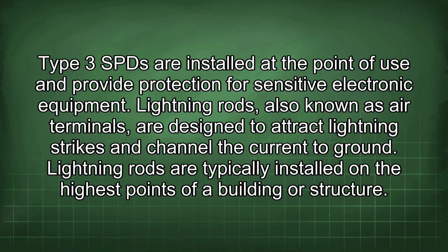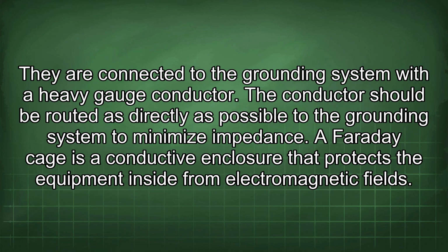Lightning rods, also known as air terminals, are designed to attract lightning strikes and channel the current to ground. Lightning rods are typically installed on the highest points of a building or structure. They are connected to the grounding system with a heavy gauge conductor. The conductor should be routed as directly as possible to the grounding system to minimize impedance.